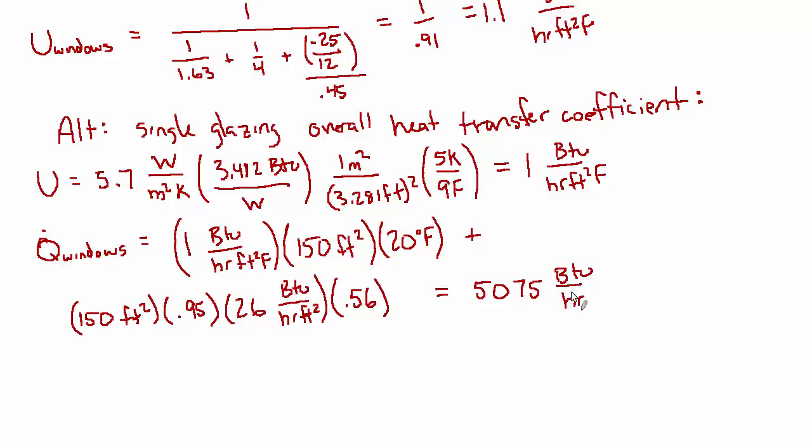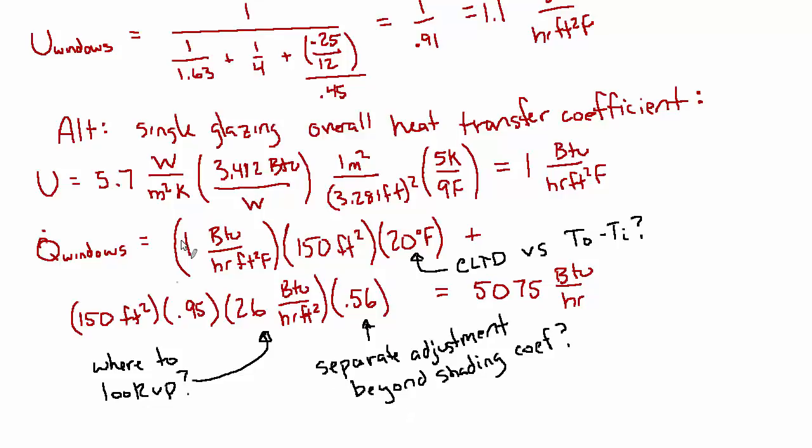This is coming from a lookup table. And the value that comes out of all that is 5075 BTU per hour. So it is a significant heat transfer through the windows. I just want to note down some of these questions in a different color. So that's which value should be plugged in here. Should it be the cooling load temperature difference or should it be the actual temperature difference? And then where do you look up the solar load factor? And then what is this separate adjustment above and beyond the shading coefficient? So those are some questions.